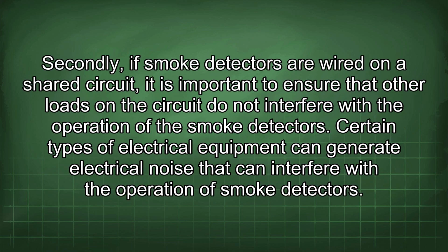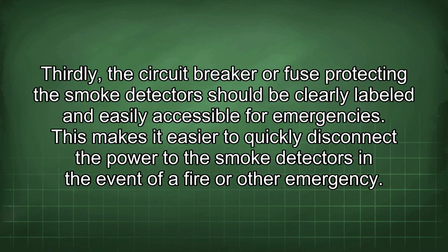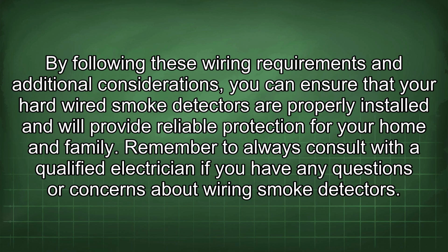Secondly, if smoke detectors are wired on a shared circuit, it is important to ensure that other loads in the circuit do not interfere with the operation of the smoke detectors. Certain types of electrical equipment can generate electrical noise that can interfere with the operation of smoke detectors. Thirdly, the circuit breaker or fuse protecting the smoke detectors should be clearly labeled and easily accessible for emergencies. This makes it easier to quickly disconnect the power to the smoke detectors in the event of a fire or other emergency. By following these wiring requirements and additional considerations, you can ensure that your hardwired smoke detectors are properly installed and will provide reliable protection for your home and family.